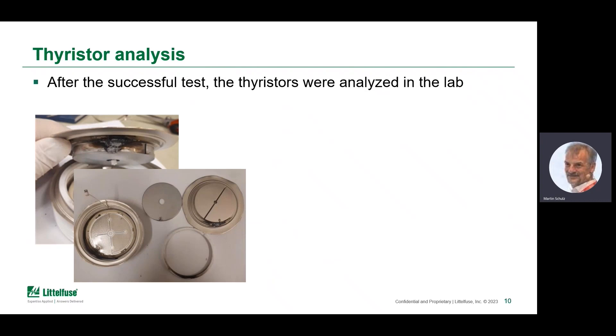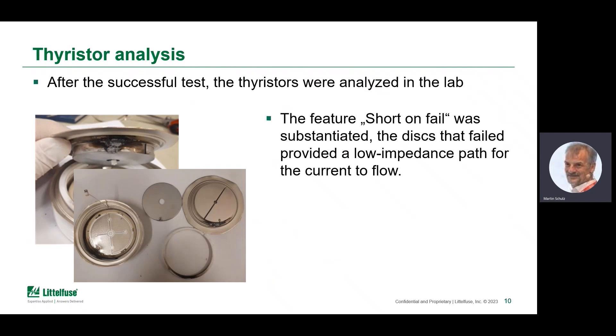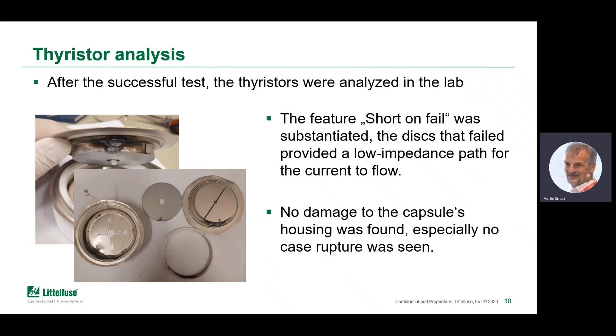However, disassembling all the components clearly showed that the case rupture enhancement that was in place really did a great job. Discs like these feature short-on-fail, and that is often said — but here it's substantiated. After the thyristor got destroyed electrically, it still formed a low-impedance path to keep up the short-circuit current up to the moment where the fuse cleared the situation. The energy set free in that case is amazingly high, but as you can also see, there is no damage done to the capsule's housing — case rupturing was prevented as demanded.